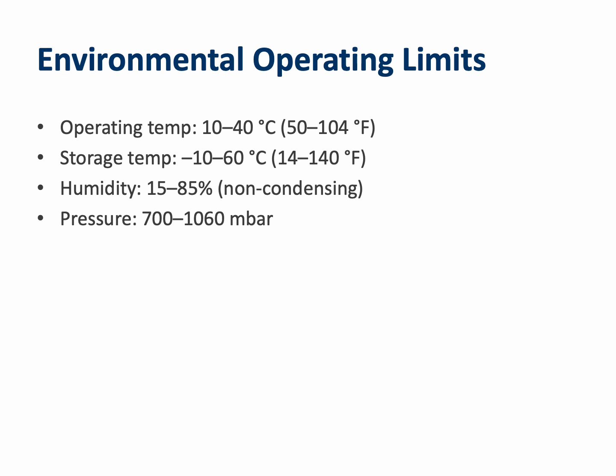Environmental parameters define where and how the FT10 can safely operate. It runs best between 10 and 40 degrees Celsius, or 50 to 104 Fahrenheit. For transport and storage, it can tolerate -10 to 60 degrees Celsius. Humidity should remain between 15 to 85%, non-condensing, which is consistent with most hospital environments. Atmospheric range is between 700 and 1060 millibars, allowing the generator to function effectively even at higher altitudes. These parameters are critical for shipping, storage, and global deployment.